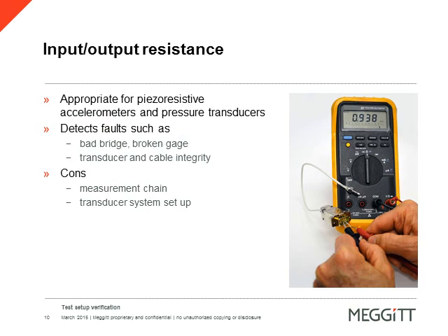Measuring input and output resistance is a great method to verify a healthy transducer. This requires the transducer's output connector be available for measurement with an ohmmeter. This resistance measurement is made at the first available connection point to the transducer. The resulting values are compared to the transducer's datasheet, and any out-of-tolerance measurement should be considered for replacement.